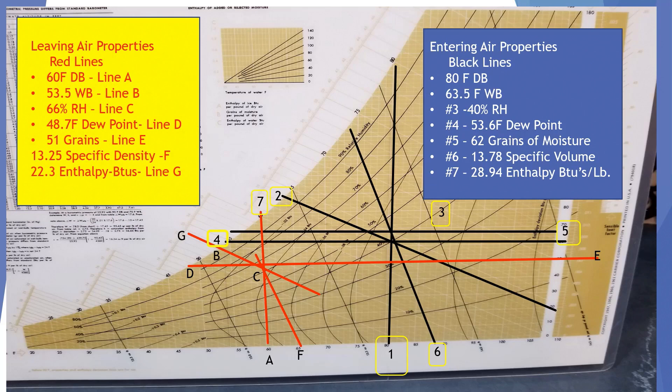On the other side of leaving air properties, which are the red lines, we have a 60 degree dry bulb temperature shown on line A. We have a 53.5 wet bulb temperature shown on line B. We have 66% relative humidity on line C. We have 48.7 degree dew point, which is line D. We have 51 grains of moisture on line E.